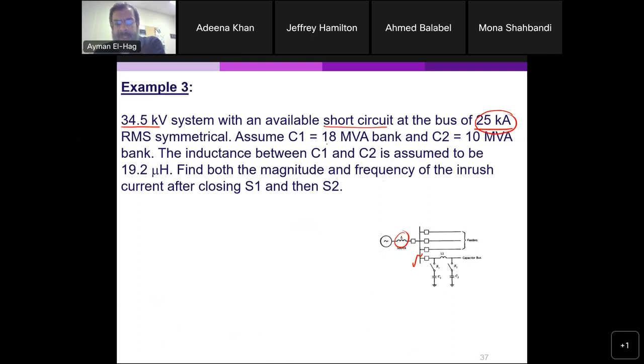Assume C1 is 18 MVA, and C2 is 10 MVA. The inductance between C1 and C2 is equal to 19.2 microhenry. Find both the magnitude and frequency of the inrush current after closing S1 and then S2. So I want to find the magnitude of this inrush current and its frequency when we do the closing, first S1 and then S2. Now S1 is very straightforward.